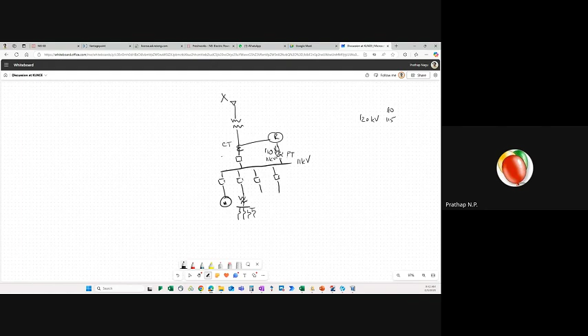But the problem here is, let's say you lose this utility. Now the power to this bus bar is lost. Power to the relay is lost. The relay is basically dead now, right? You cannot do anything. And now let's say the power comes back. The relay takes probably 5 to 10 seconds, or maybe even more, to boot up and load its program, refresh everything, all the status of the digital inputs, analog inputs, everything. And by the time a fault occurs there, it is not going to see the fault current. So it is not going to issue a trip signal to this breaker.